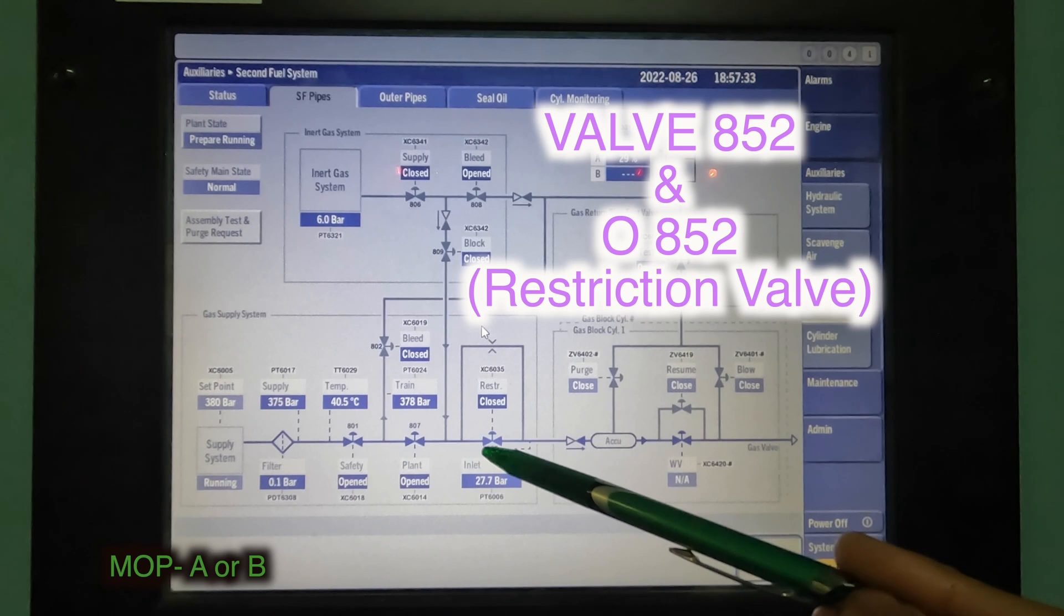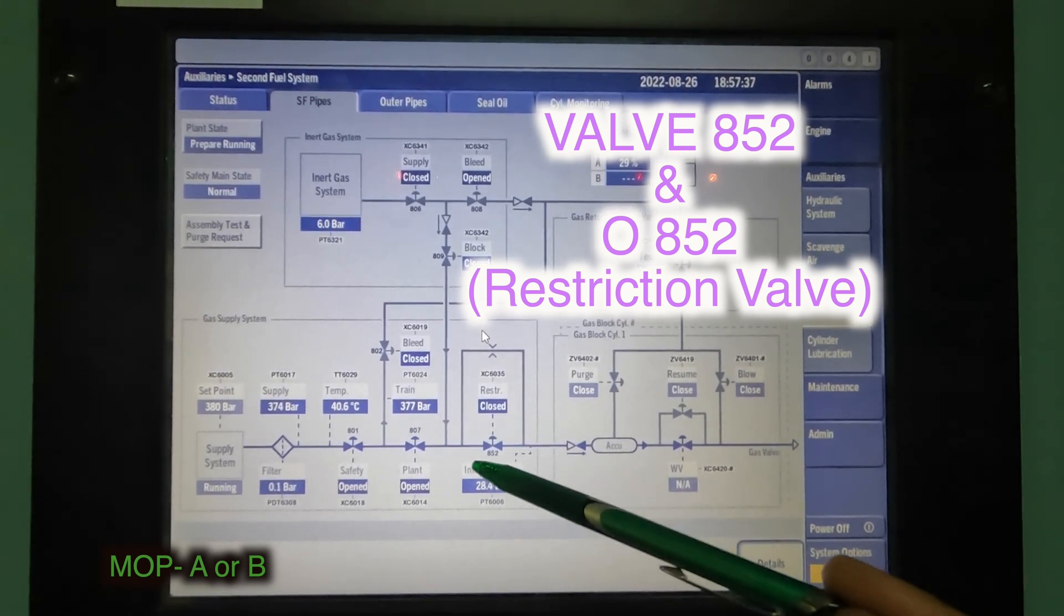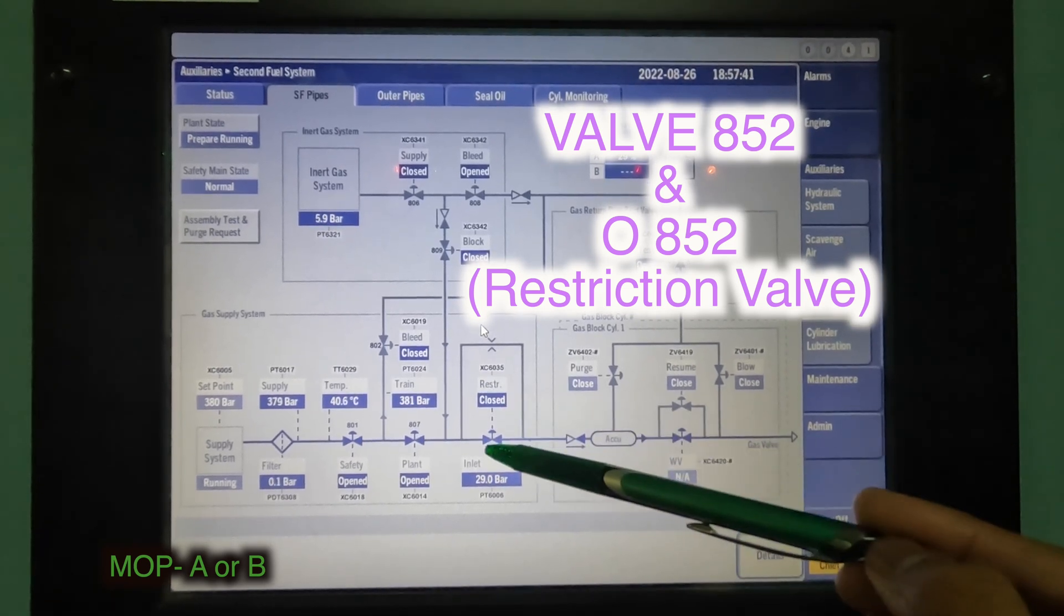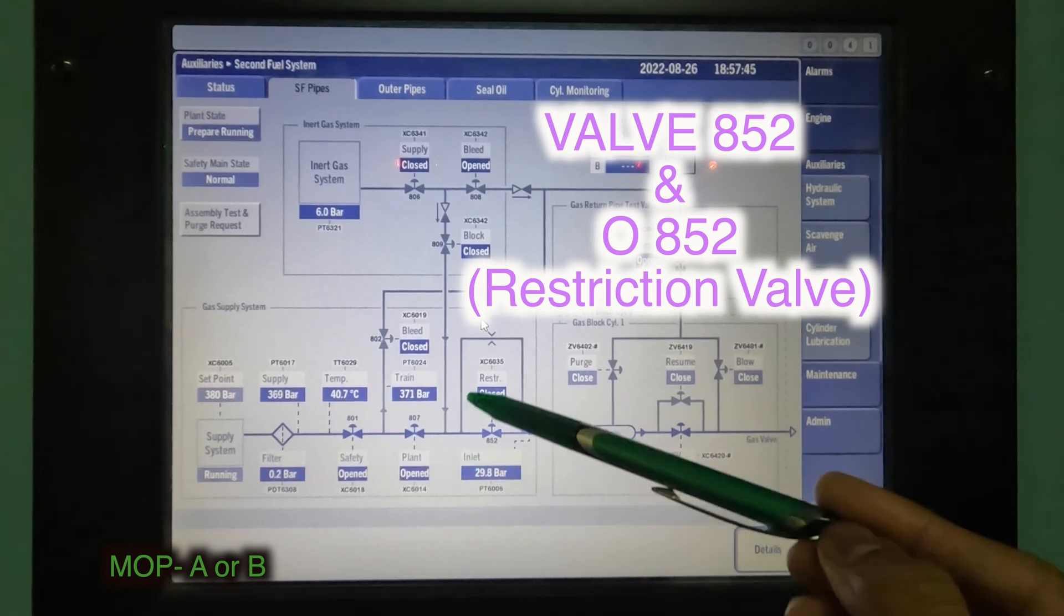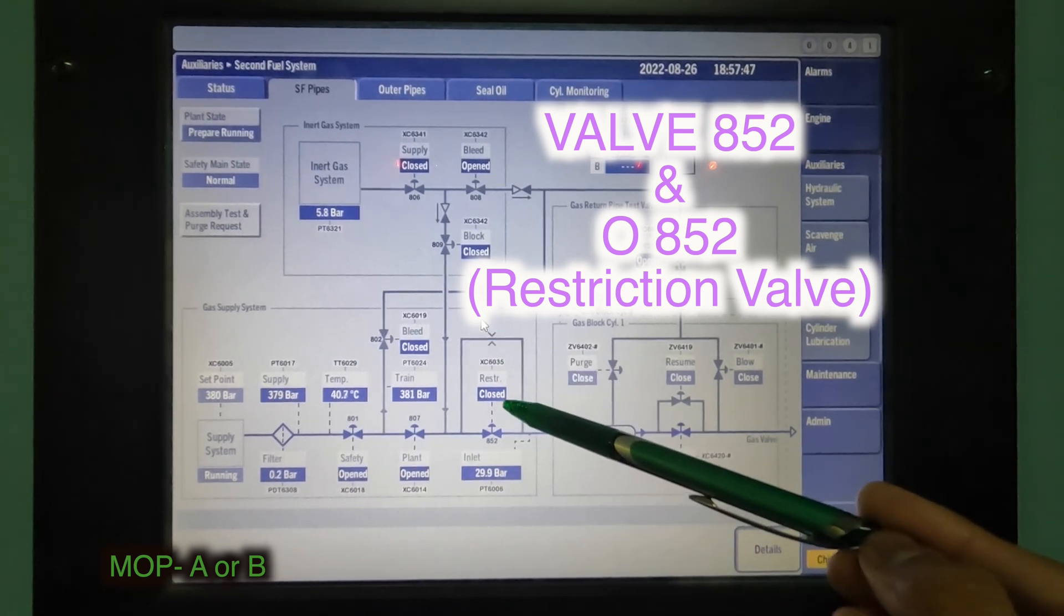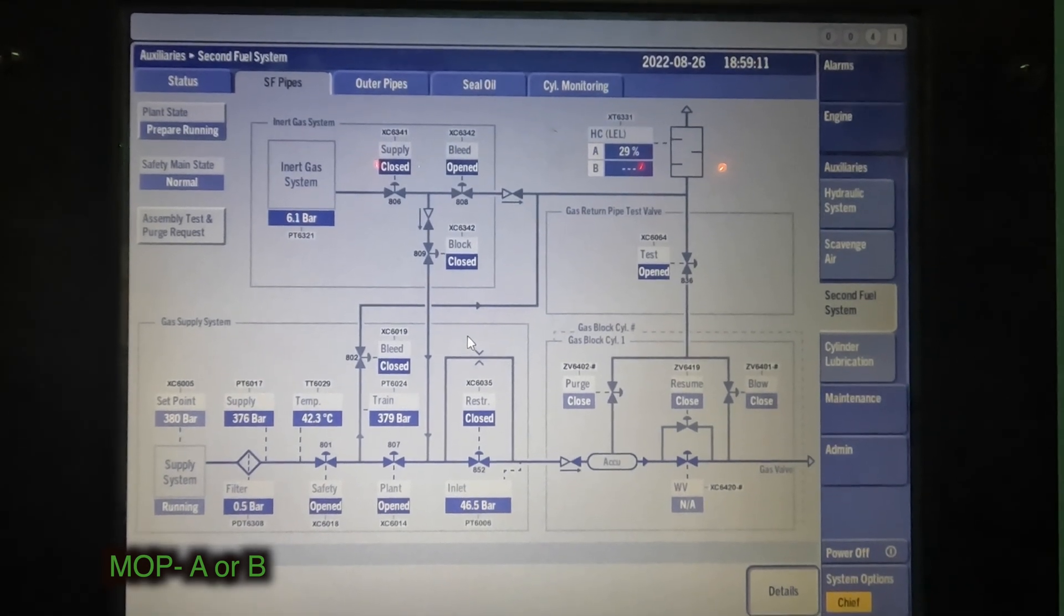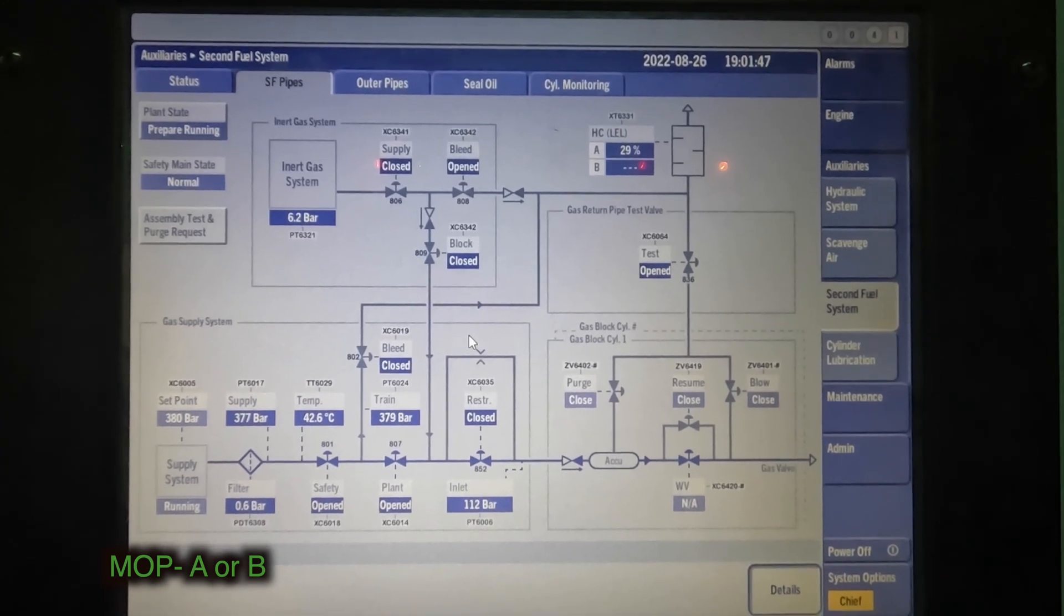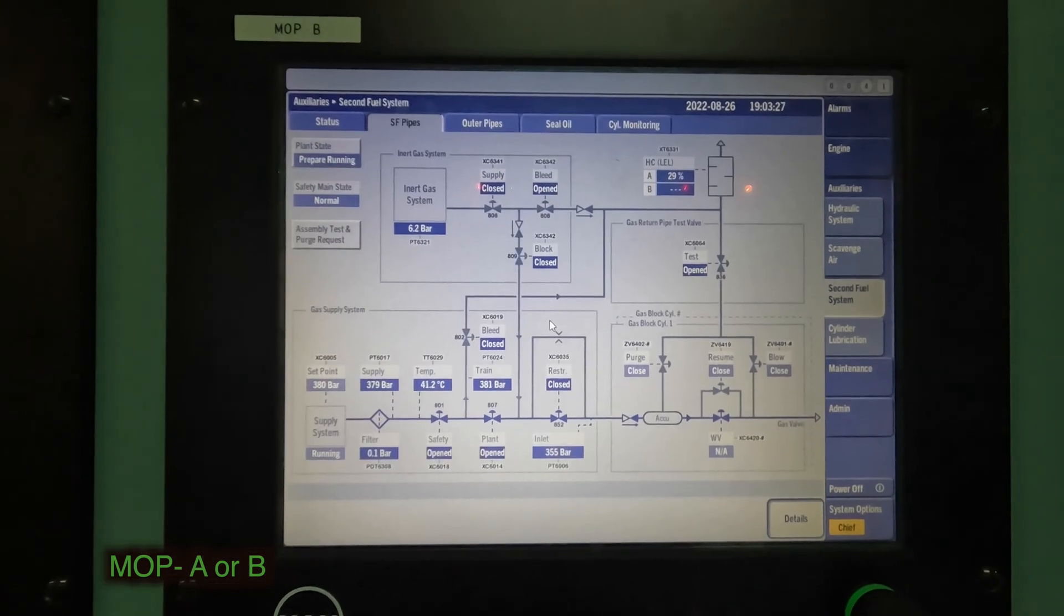This happens because we don't want, once this valve opens, we just don't want 380 bar to come here and shoot on this side. This will cause a high pulsation, high pulse with 380 bar and a sudden drop on this side. And hence, we have a restriction valve on that side. Okay, so time to speed up again. We see the pressure building up right up to 380 bar from the orifice valve and once it's 380 bar, you'll get a moving signal on 852 and that's when the engine is ready to fire.